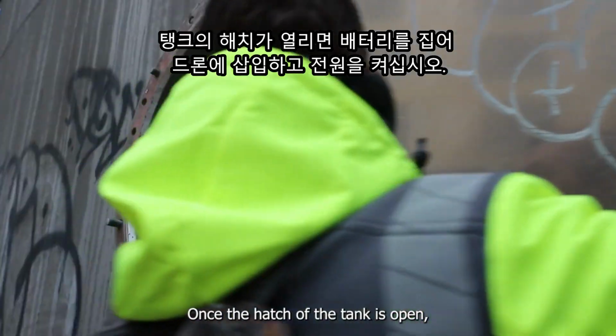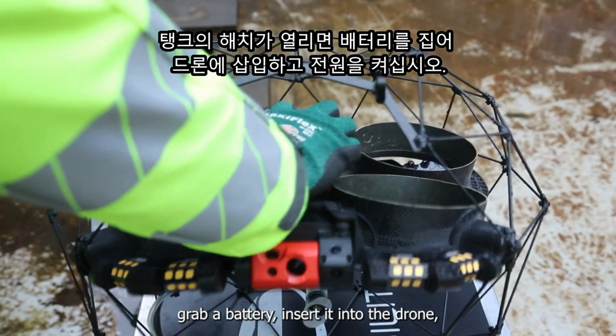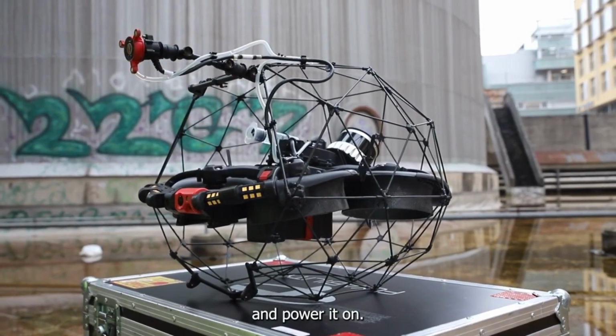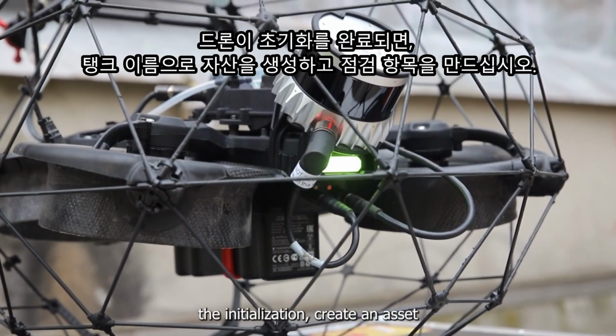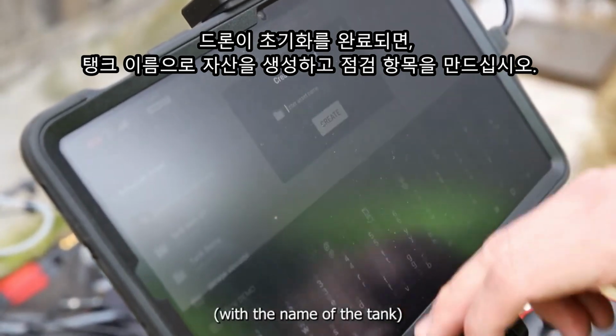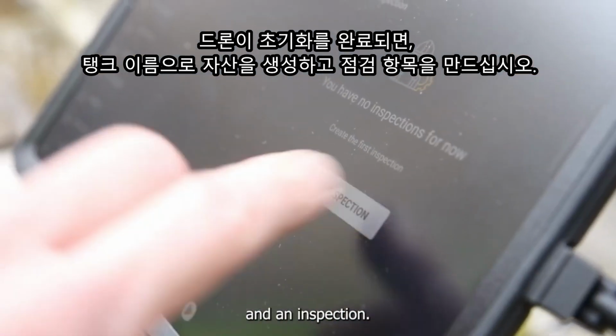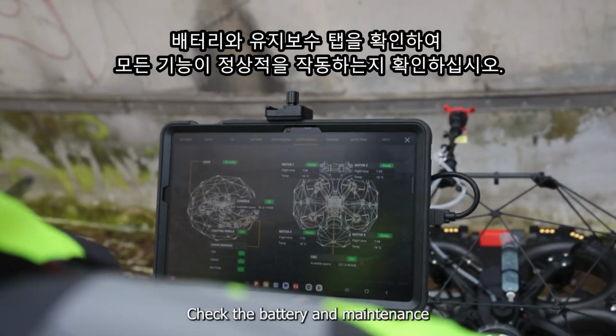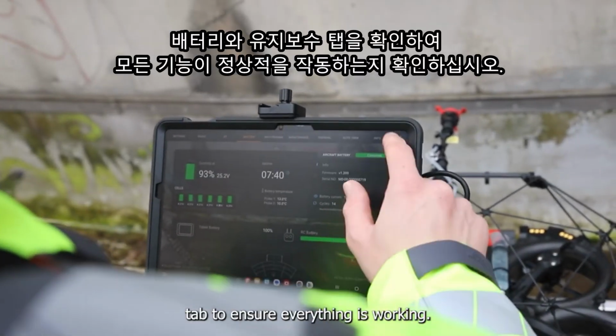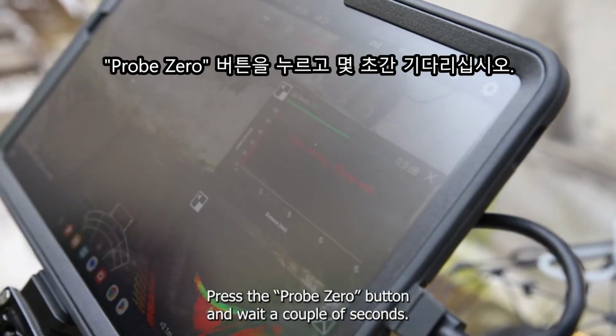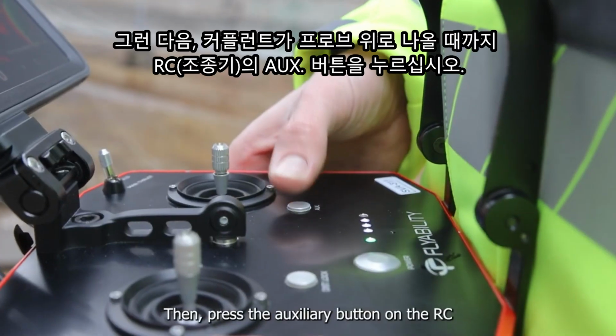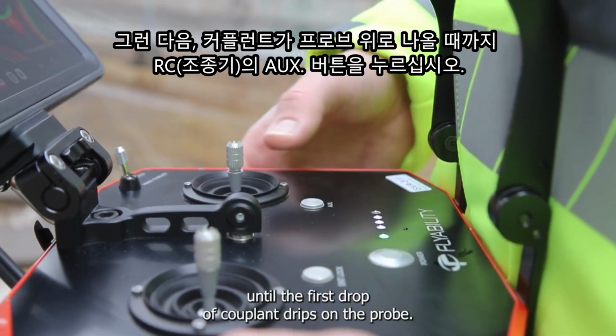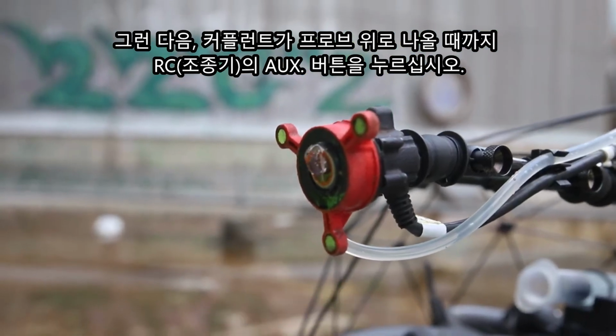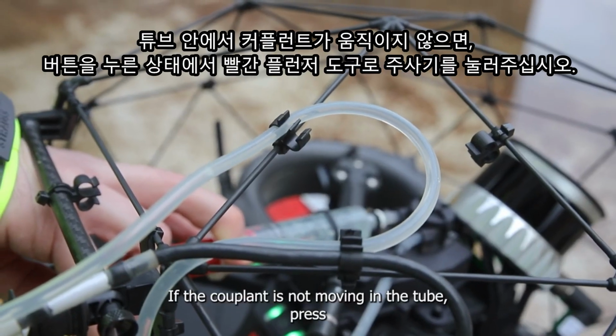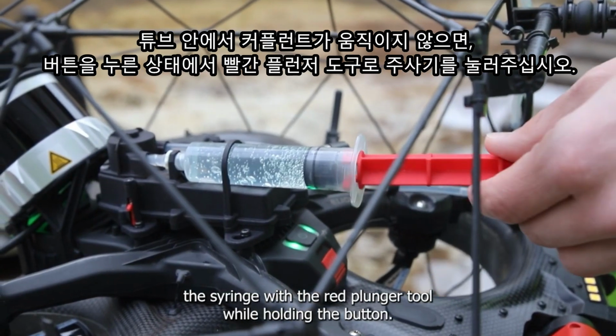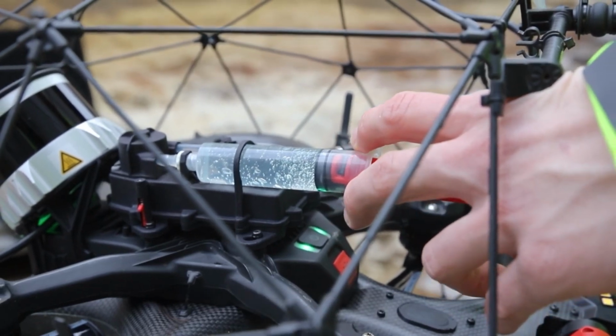Once the hatch of the tank is open, grab a battery, insert it into the drone, and power it on. After the drone finishes the initialization, create an asset with the name of the tank and an inspection. Check the battery and maintenance tab to ensure everything is working. Press the Probe Zero button and wait a couple of seconds. Then, press the auxiliary button on the RC until the first drop of couplant drips on the probe. If the couplant is not moving in the tube, press the syringe with the red plunger tool while holding the button.